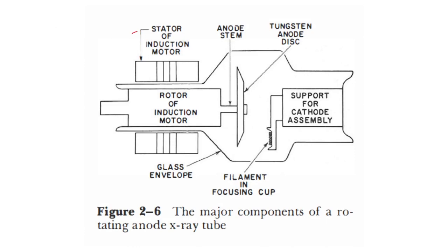We know we have started using focusing cups so that the electrons are actually focused at a particular point in the anode, at a confined point in the anode. But in reality, will each and every electron hit the target? Mostly we have designed the focusing cup in such a way that it hits the target anode. Good. But we have X-rays which are produced.